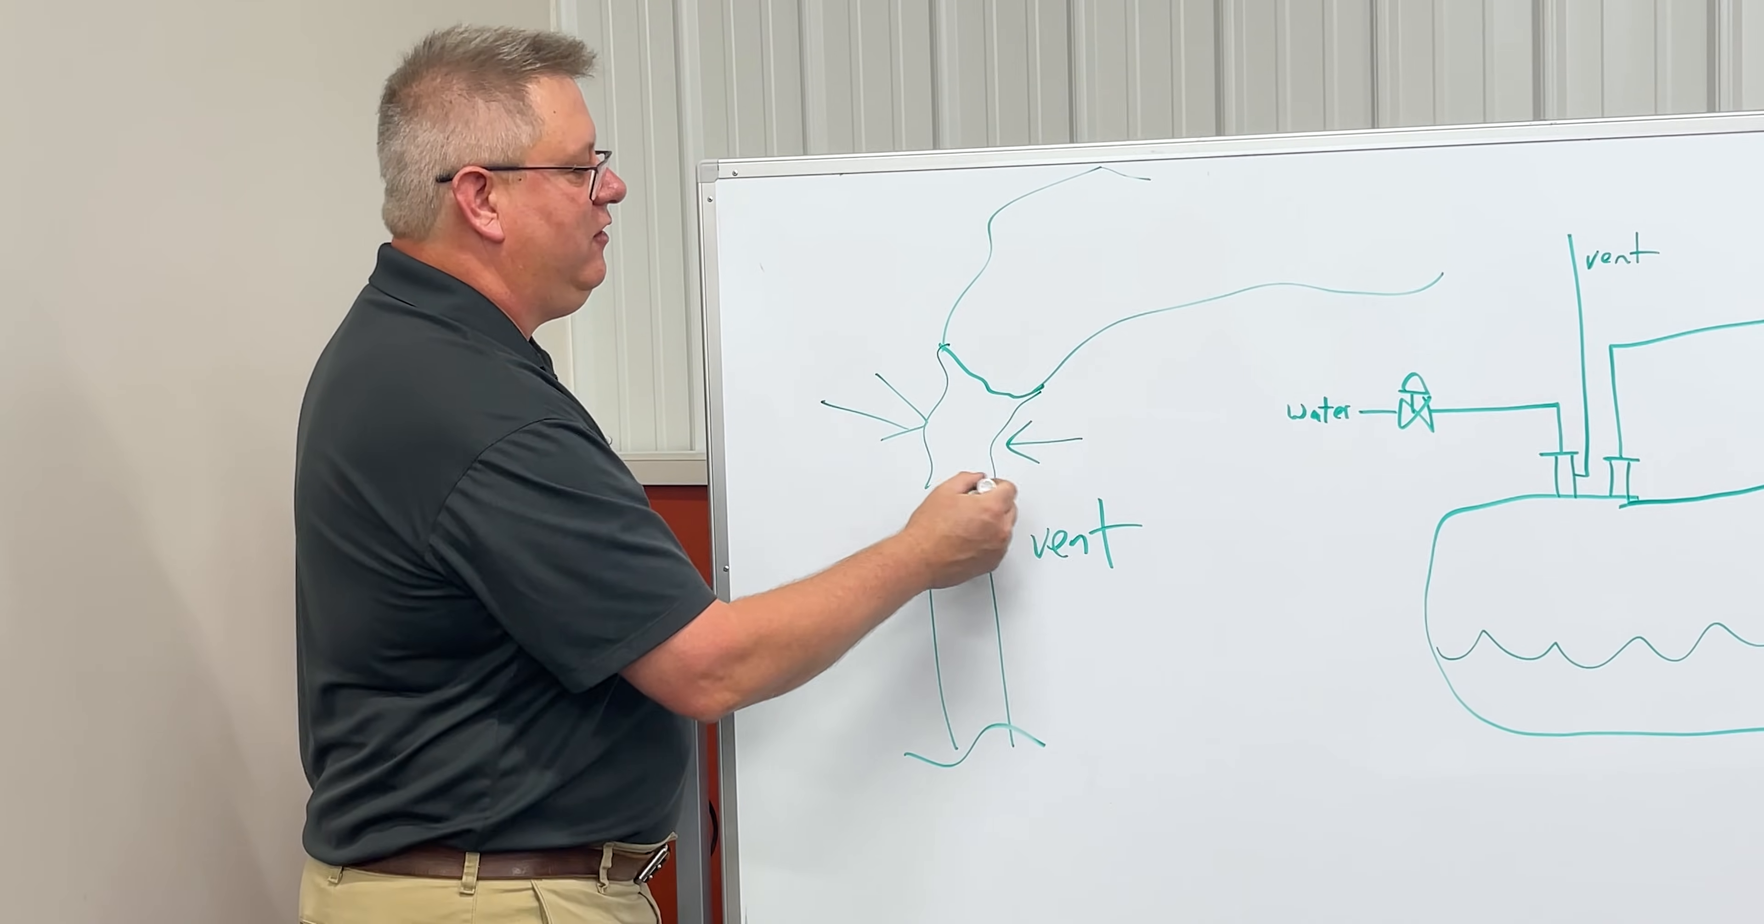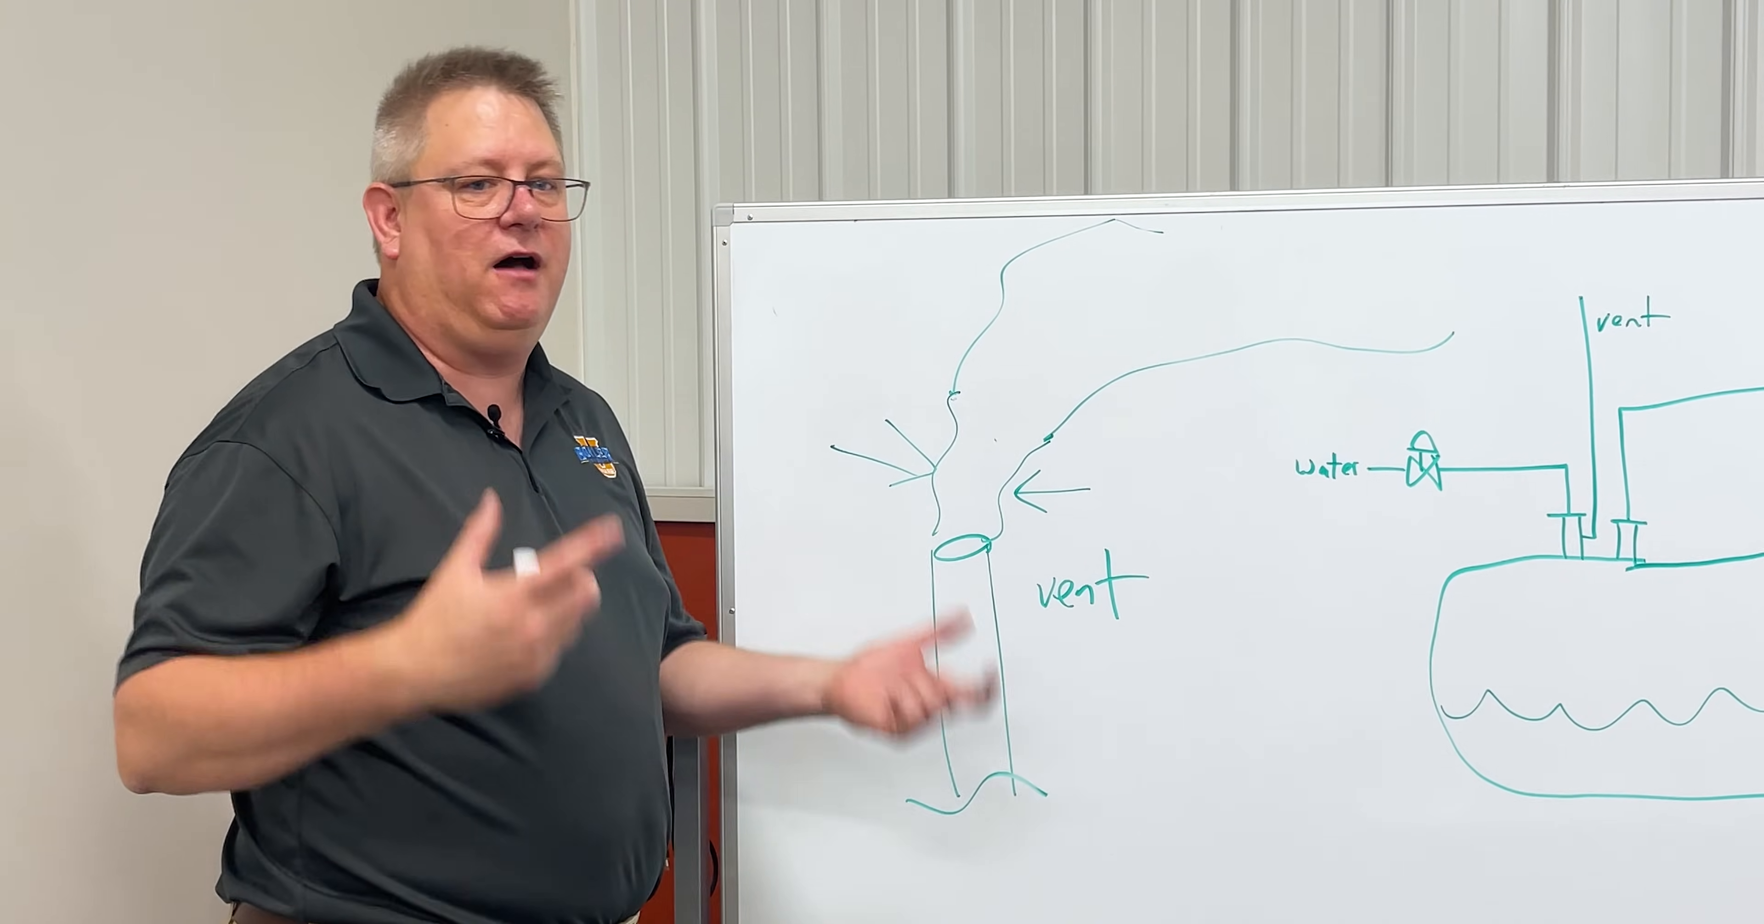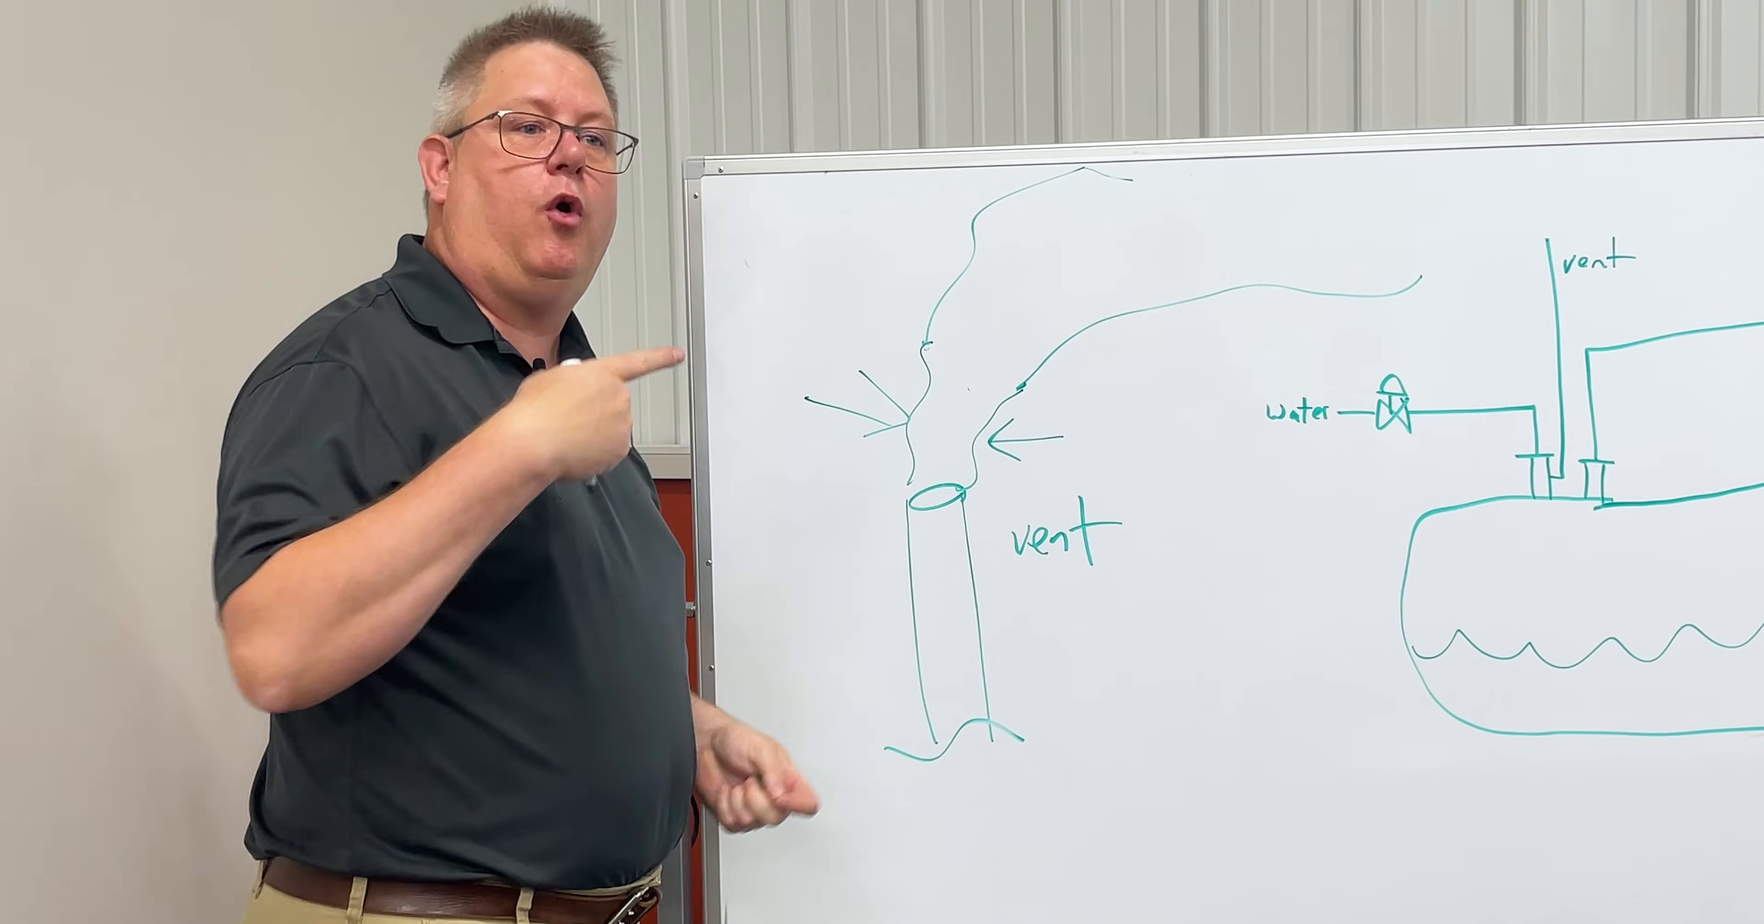That orifice is sized for the normal makeup on the deaerator. If you purchased that deaerator and it was stated you were going to have 60% makeup, but in reality you've got 100% makeup, that vent is going to have to be open farther or you're going to need a bigger hole in the seat of the vent. Just keep in mind it was designed to be closed with the orifice in the valve doing the job.